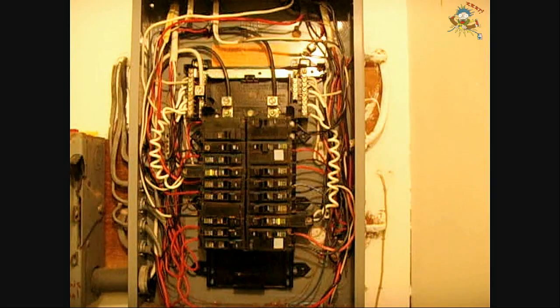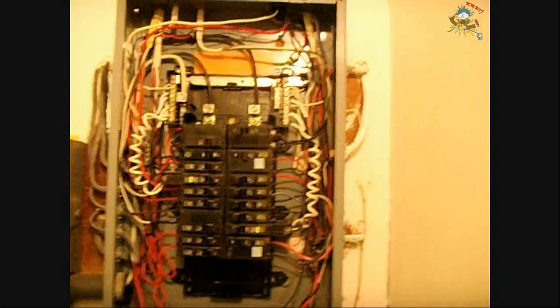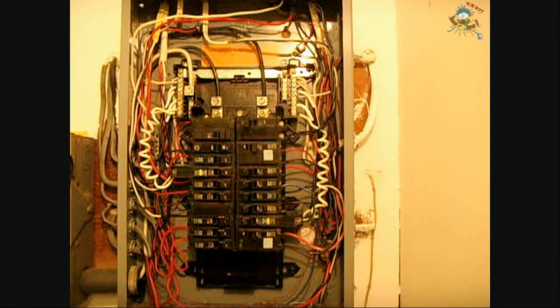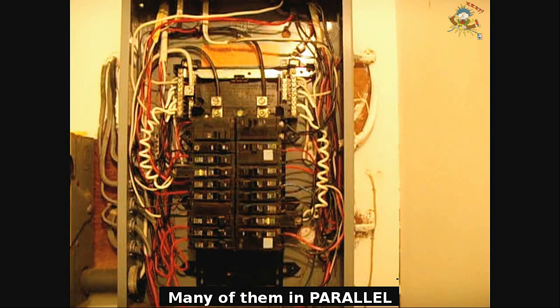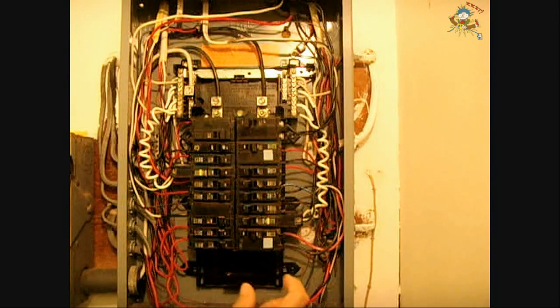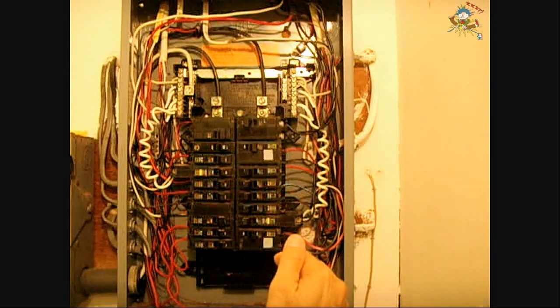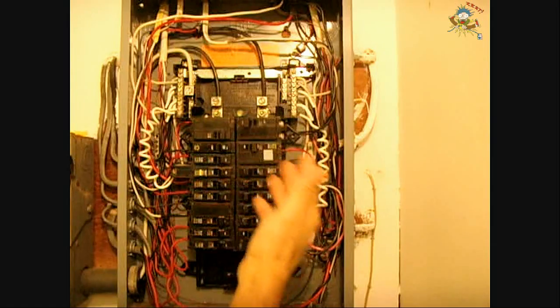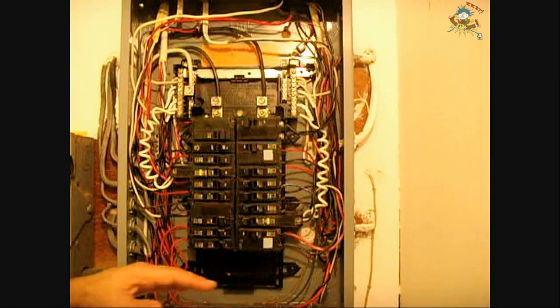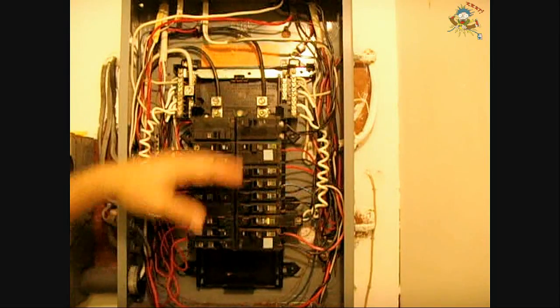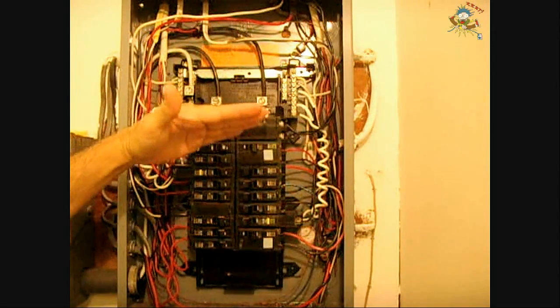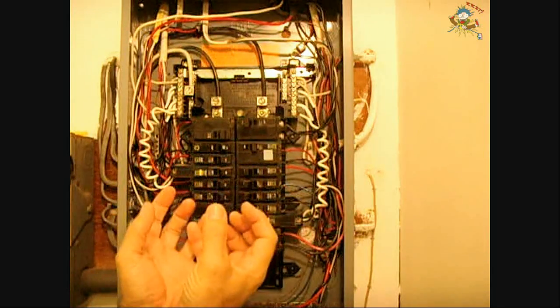Now I also have on this panel, you can't see it, I'll tilt up just a little bit, right at the top right there, that is a surge arrestor, for if there's a surge coming through the power supply into this house. Now what's inside there is a component called a varistor. Varistors are designed so that when voltage is kept below a certain level, the resistance of that component is extremely high. As the voltage climbs, as in a surge, maybe 275, 300 volts or higher, instead of everything experiencing that surge, the surge arrestor more or less acts like a shock absorber. It takes that pressure, which is actually higher voltage, and it suppresses it.